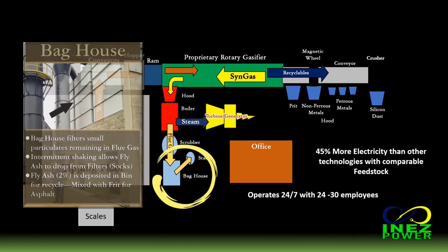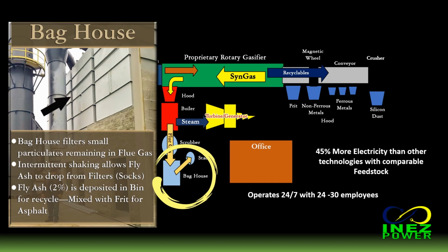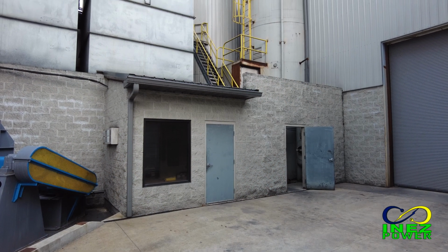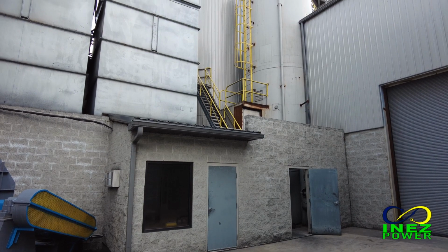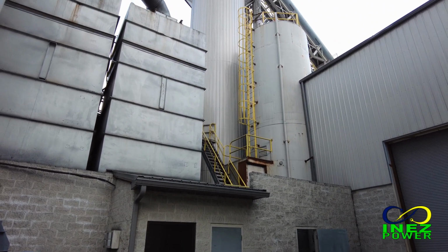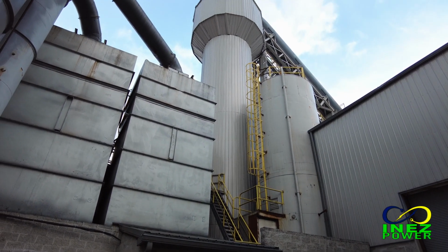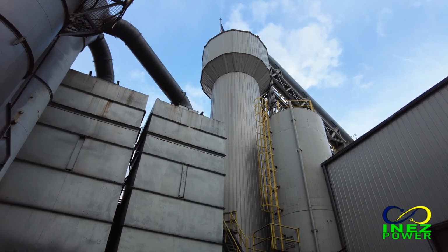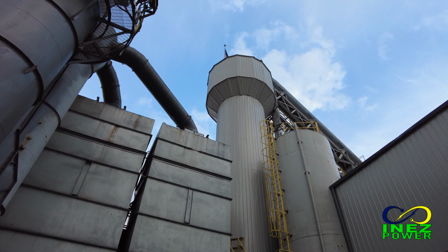From the spray dryer absorber, the treated flue gas is ducted to a multi-chamber baghouse for the final removal of any remaining contaminants. Inside the baghouse, the gases pass through filters to remove particulate matter. Particulates, including the ash collected inside the baghouse, are transported by conveyor belt to the fly ash bin.